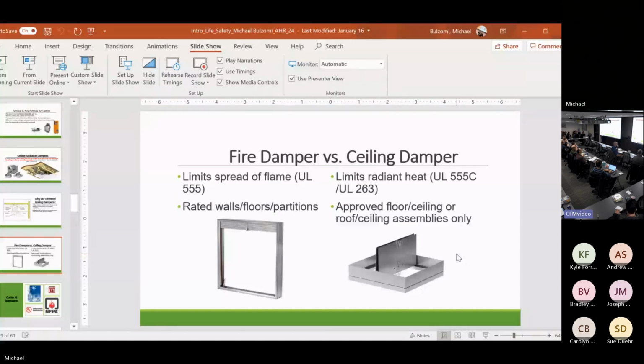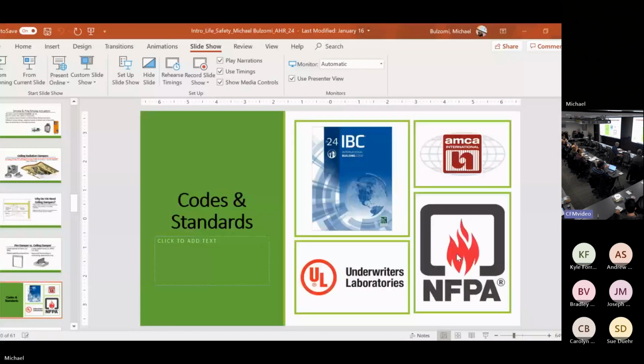So never allow that in a submittal. Never allow that in a walkthrough. Anybody ever asks you, can I use a horizontal fire damper in place of a ceiling radiation damper? No, there is never an acceptable answer where a fire damper can be used in place of a ceiling damper. One takeaway everyone's going to walk away with today, right?